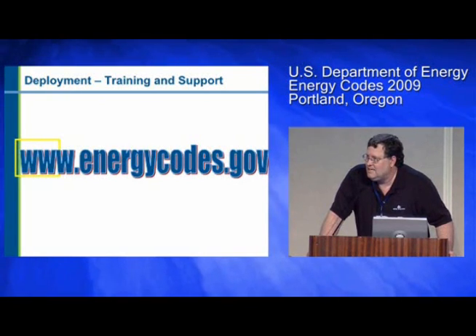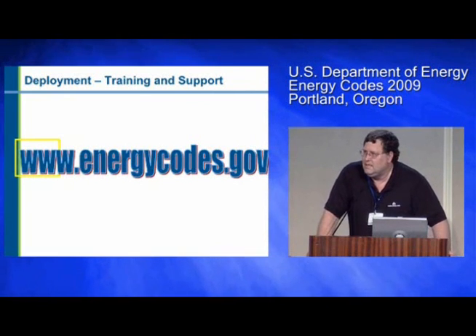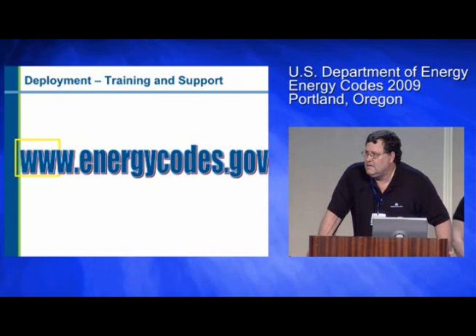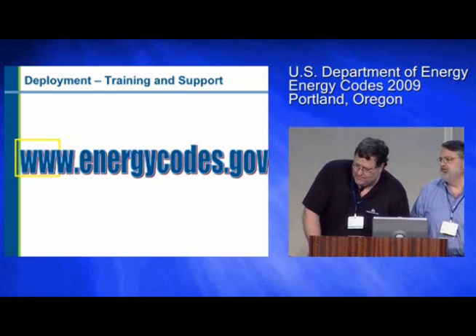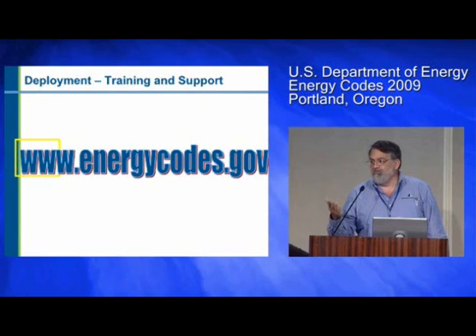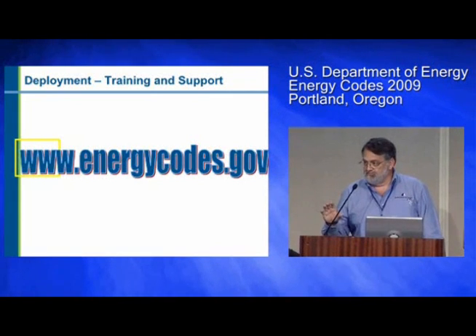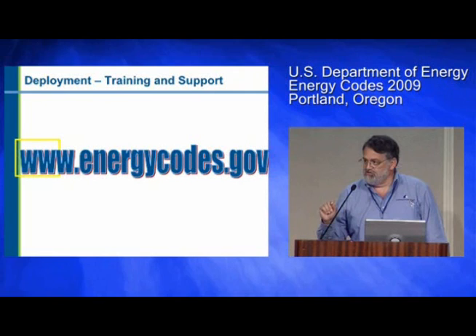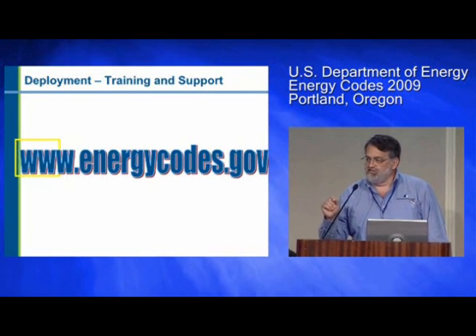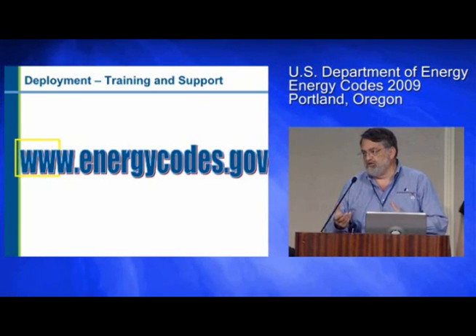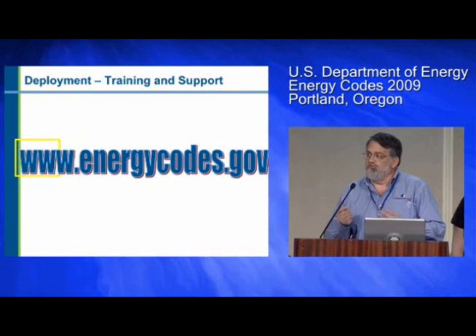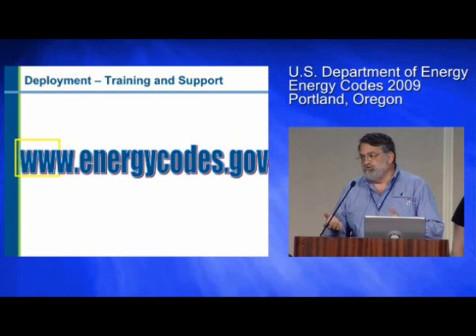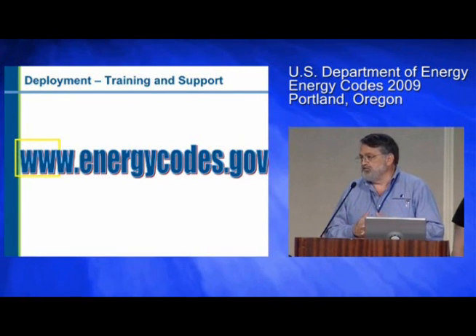Going back to the external lighting zones, on the internal lighting zones, there is a provision for safety purposes, where you address things like parking lots, where low lighting levels could be a safety issue. Therefore, you would need a higher light level. Or that's an Eric question, thankfully. Yeah. All of the LPD requirements, interior and exterior, are based on IES light level requirements. And there is a G1 security light level document, which in some cases a building owner will realize they're in that capacity, although it rarely happens. In that case, if there is a security requirement, that would overshadow the energy requirements. But generally, for most applications, they're based on IES requirements, and that's the standard of care for the industry.